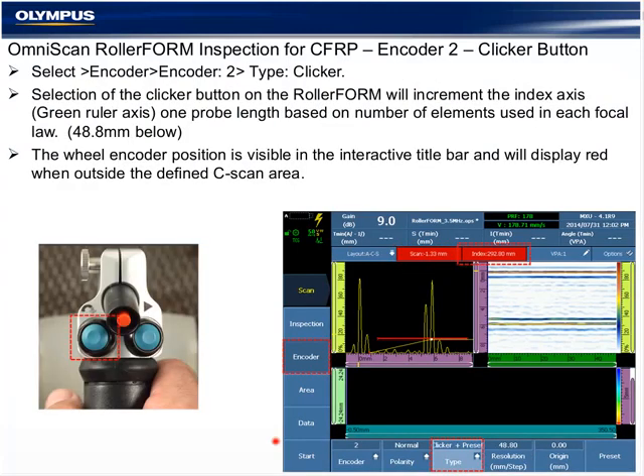Okay. Select Scan Encoder and change from encoder 1 to encoder 2. Encoder 2 is going to be a clicker and preset type encoder, and it has a resolution here that's automatically determined by the software based on the phased array configuration. We're going to talk about this a little bit more in a few slides, but the software knows at this point that center beam 1 to center beam 2, or center beam last, is 48.8 millimeters. So every click of this button will index the index axis position 1 stroke, or 48 millimeters, as it's incremented.